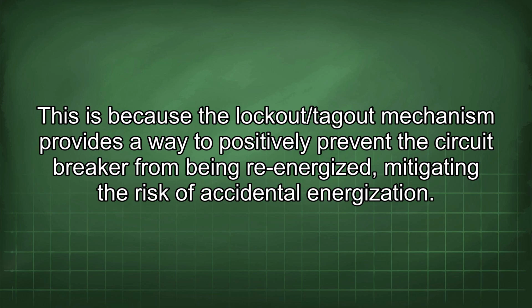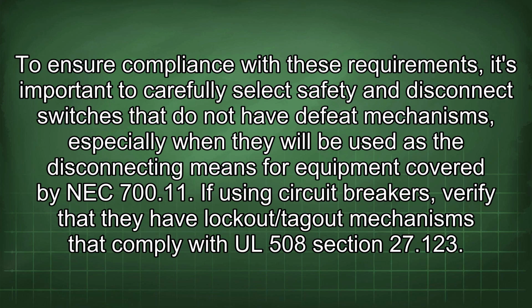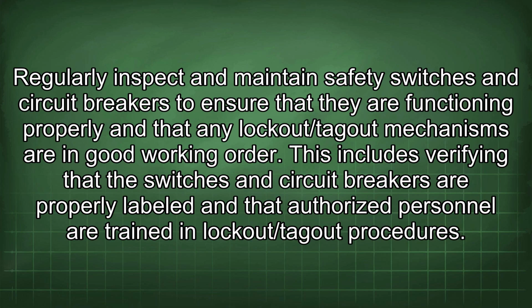risk of accidental energization. To ensure compliance with these requirements, it's important to carefully select safety and disconnect switches that do not have defeat mechanisms, especially when they will be used as the disconnecting means for equipment covered by NEC 700.11. If using circuit breakers, verify that they have lockout/tagout mechanisms that comply with UL 508 Section 27.123. Regularly inspect and maintain safety switches and circuit breakers to ensure that they are functioning properly and that any lockout/tagout mechanisms are in good working order.